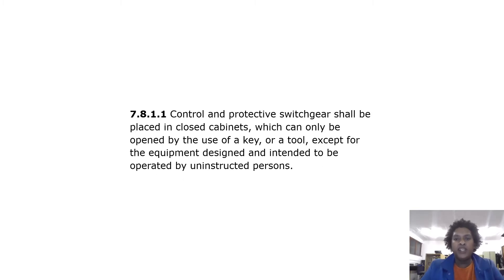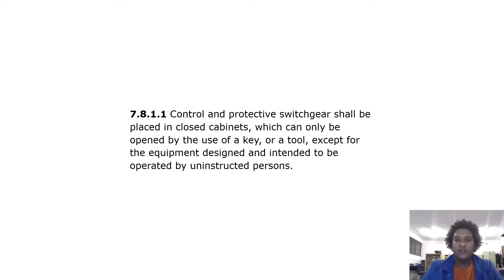Control and protective switchgear shall be placed in closed cabinets which can only be opened by the use of a key or a tool, except for equipment designed and intended to be operated by uninstructed persons.